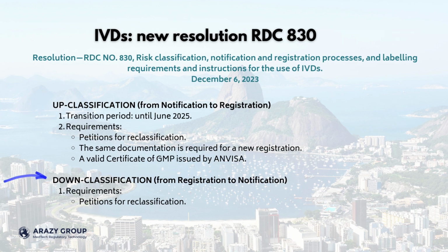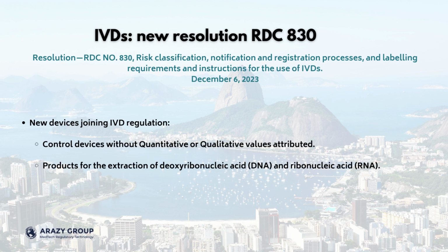Down classification. Registration processes whose products had their regularization regime modified from registration to notification due to the classification rules will be dealt with by means of a petition for reclassification by ANVISA. The following two devices are now, under this new resolution, RDC 830, classified as IVDs and must be duly regularized within 365 days from the entry into force of this resolution, which means by June 2025.